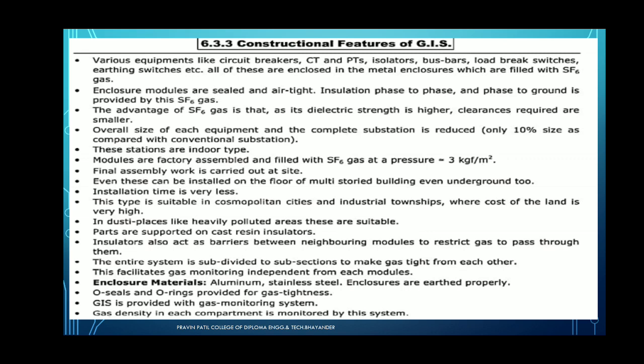Even these can be installed on the floor of a multi-storey building, even underground too. Installation time is very less. This type is suitable in cosmopolitan cities, industrial townships where the cost of the land is very high. In dusty places like heavily polluted areas, these are also suitable for the gas insulated substation. Parts are supported on the cast resin insulator. Then the insulator also acts as the barrier between the neighboring modules and restricts gas from passing through them. The entire system is subdivided into subsections to make them gas tight from each other. This facilitates gas monitoring independent for each module.